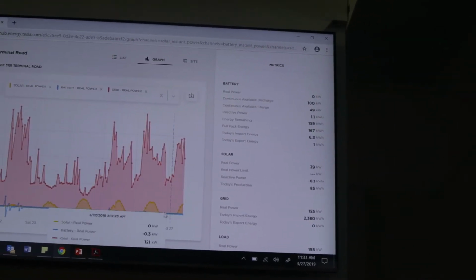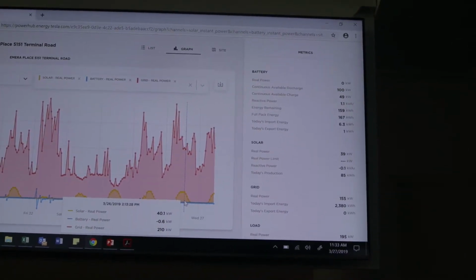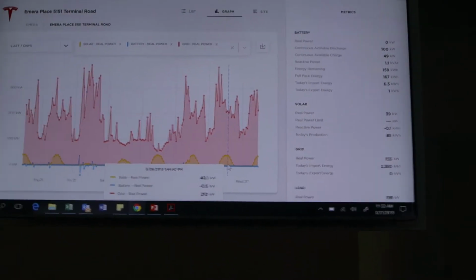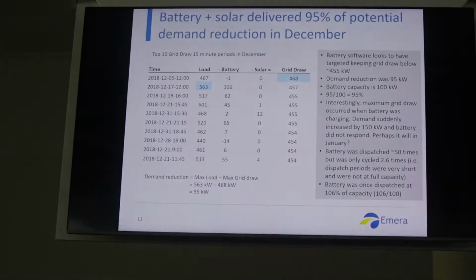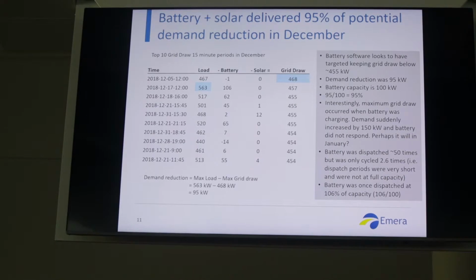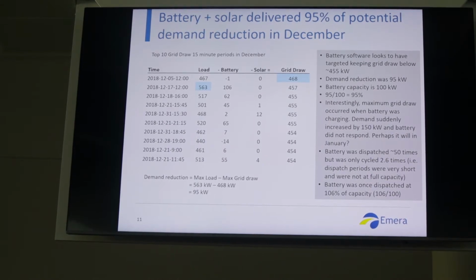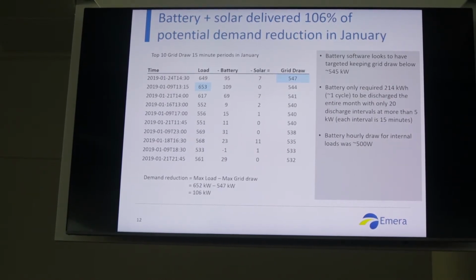The system is used for peak shaving, meaning they discharge the battery to power the building when demand is over the monthly set limit, while charging it when building demand is low. Overall, the power pack experiences a full cycle every month. Although they said this is to reduce battery degradation, we feel they should cycle more to get their return sooner.